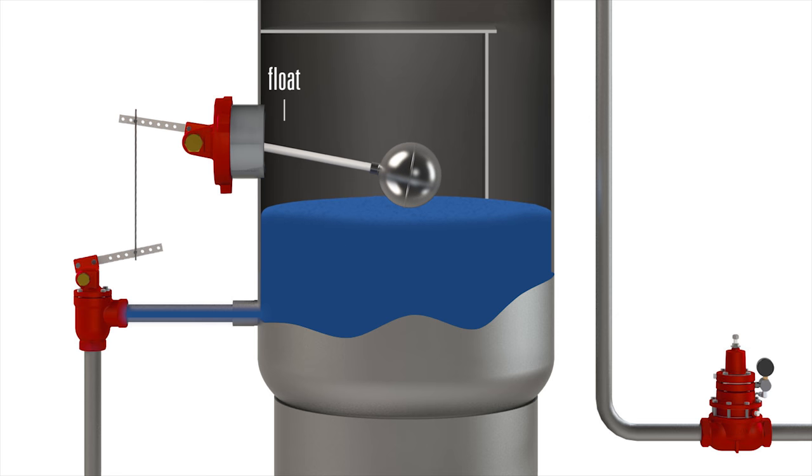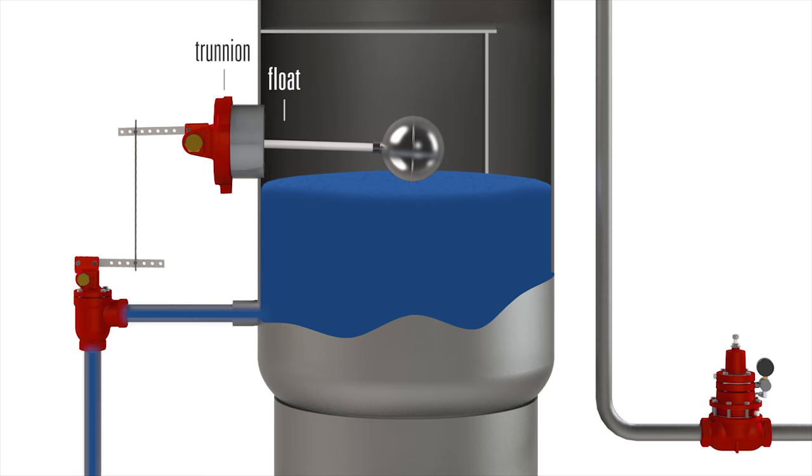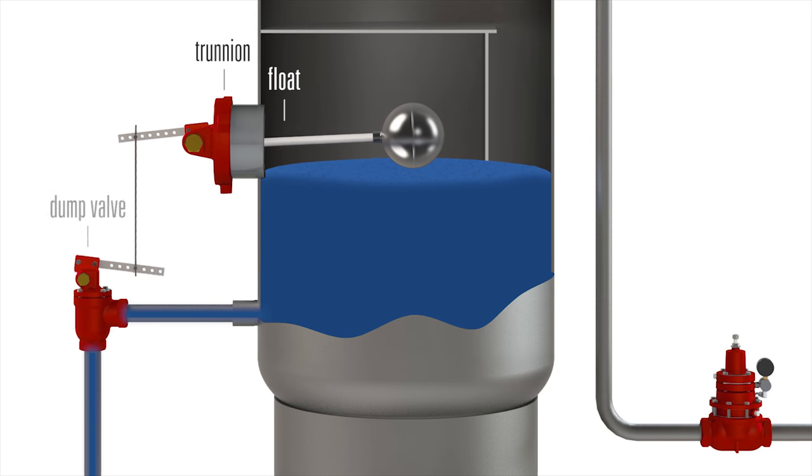A float inside a vessel moves up and down based on the liquid level. This moves the lever on the trunnion assembly, which is mechanically linked to the lever on the valve by a linkage rod.